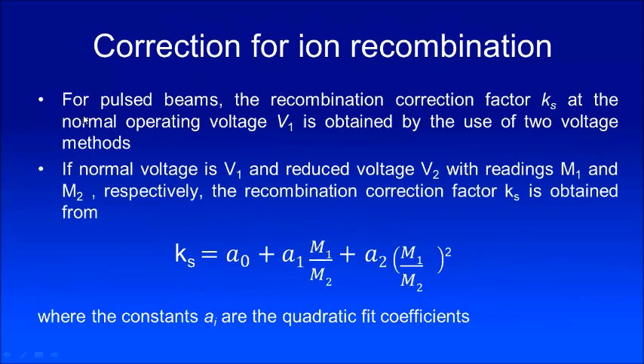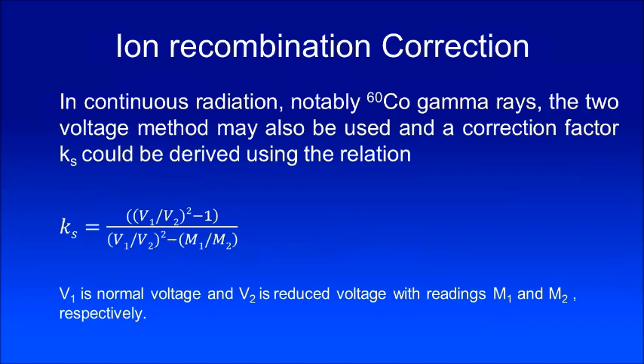For a continuous beam like Cobalt-60, you still use the two-voltage method, but the equation is different: K_s equals (V1/V2)² − 1 divided by (V1/V2)² − M1/M2. V1 is the normal voltage (e.g., +300 V), V2 is the reduced voltage (e.g., +100 V), and M1, M2 are the readings for V1 and V2 respectively.